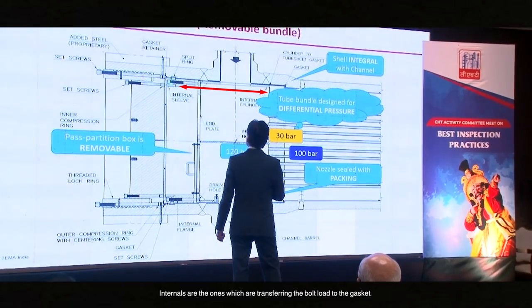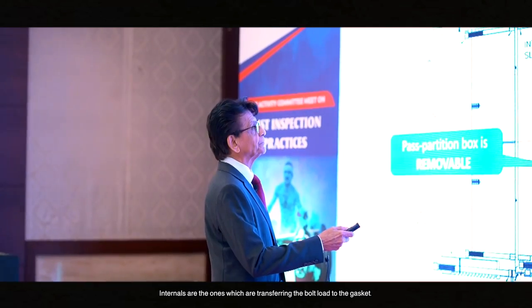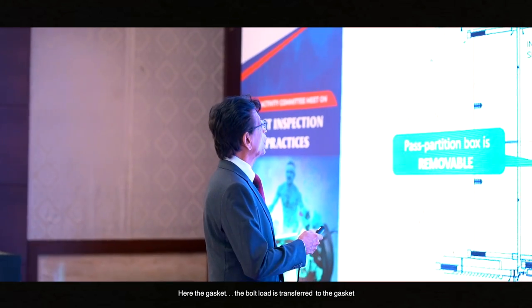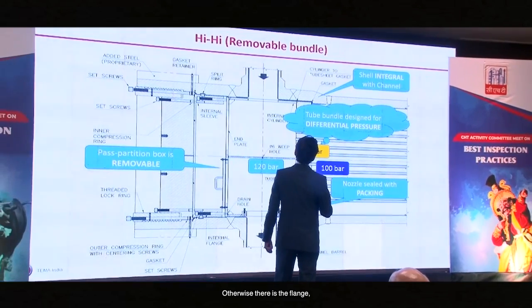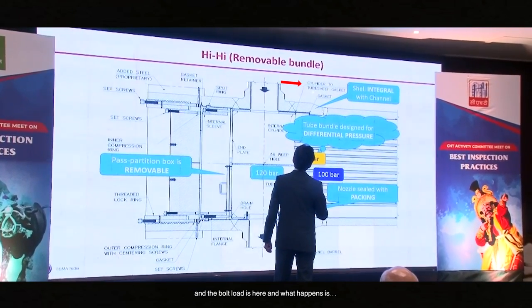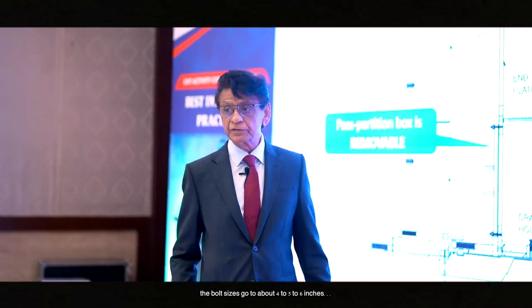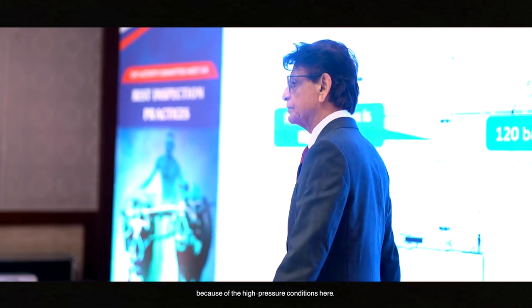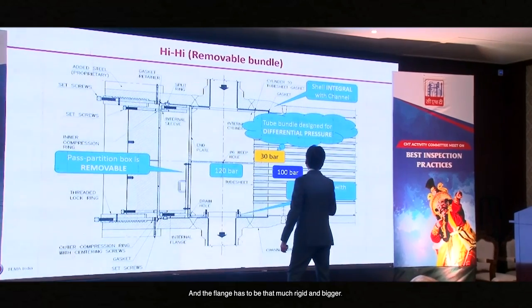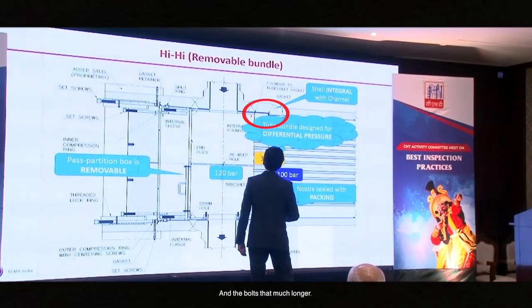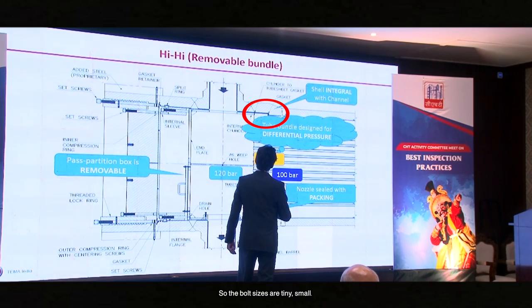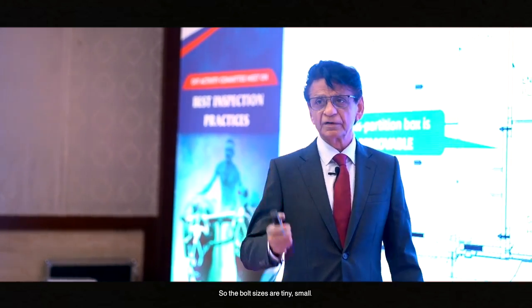The internals are the ones which are transferring the bolt load to the gasket. The bolt load is transferred to the gasket because it goes right at the center of the gasket. Otherwise, if there is a flange, the bolt load is offset. What happens is the bolt sizes go to about 4 inches, 5 inches, 6 inches because of the high pressure conditions, and the flange has to be that much bigger and rigid. Here, the load is right at the center, so the bolt sizes are tiny and small.